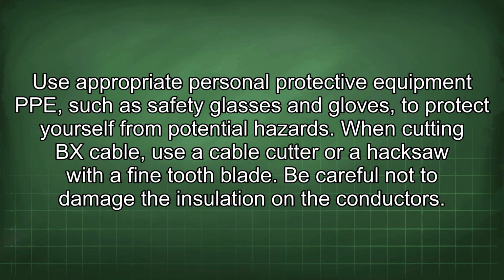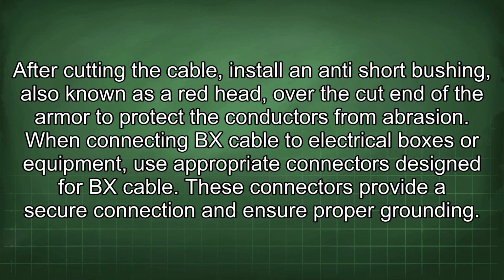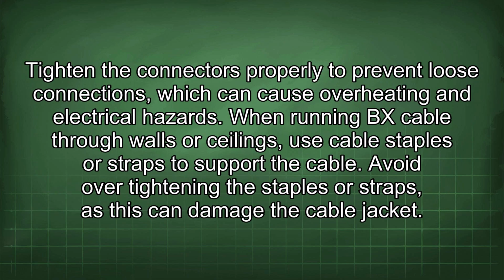When cutting BX cable, use a cable cutter or a hacksaw with a fine-tooth blade. Be careful not to damage the insulation on the conductors. After cutting the cable, install an anti-short bushing, also known as a red head, over the cut end of the armor to protect the conductors from abrasion. When connecting BX cable to electrical boxes or equipment, use appropriate connectors designed for BX cable. These connectors provide a secure connection and ensure proper grounding. Tighten the connectors properly to prevent loose connections, which can cause overheating and electrical hazards.